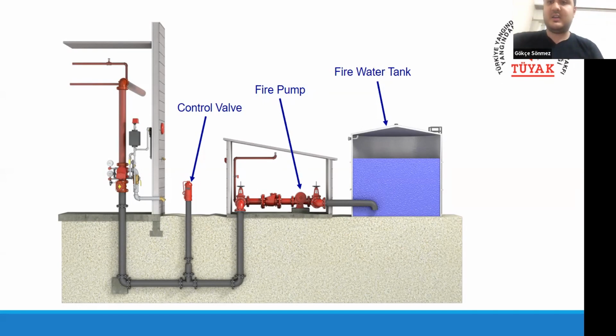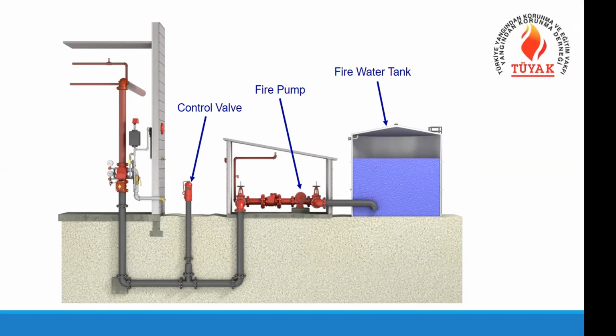Okay, and the same student is asking about the capacity of the tank. The capacity is defined by the system type. For example, for a car park, it's a 144 square meter operation area and 5 liters per minute per square meter, and it's 1 hour operation time. So it makes 43 tons minimum, for example. That depends on the building type, what kind of systems you operate, whether you have outside or inside hose connections.